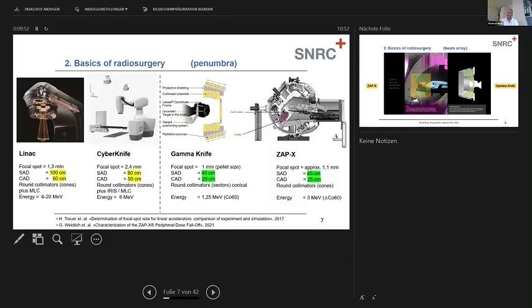So if you look at Linac versions and adapted versions, you still have the distance of 100 centimeters from the source to the target. This has to be because otherwise you wouldn't be able to treat prostates, for example. Then CyberKnife as being the representative of a dedicated device to treat the whole body. And on the right dashed line, you see the dedicated devices for brain only, which would be the GammaKnife and the ZAP. And you see the distance from the source to the so-called unit center point is much smaller, 40 and 45 centimeters. So this does have an impact on the quality of the penumbra.